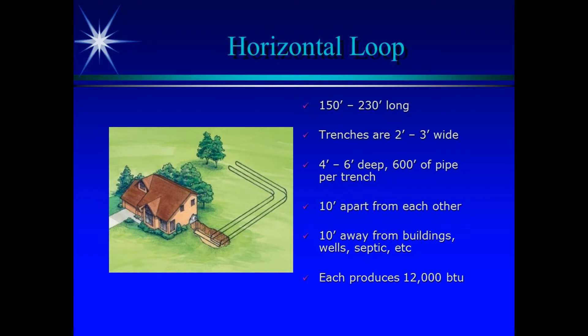So 10 feet is a proper distance for that. Each one of these configurations is about 12,000 BTUs. What does that mean? The average system up here, correct me if I'm wrong, is about a 4-ton geothermal system, maybe 3 to 4, on our average size home. So a 4-ton system means you're going to have 4 of those trenches, 10 feet apart, so you've got at least 40 feet that way, and anywhere from 150 to 230 feet long, depending on where that's at.